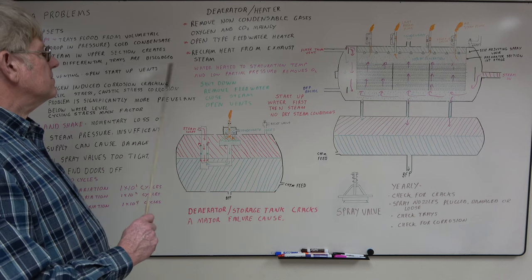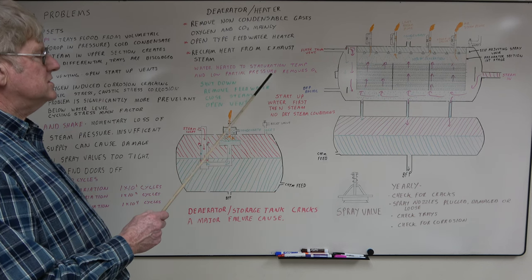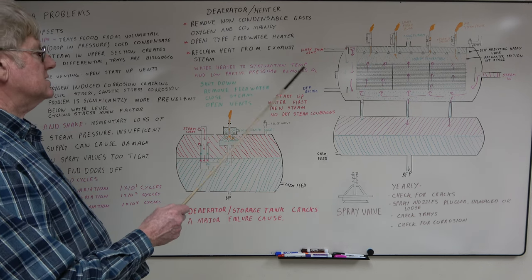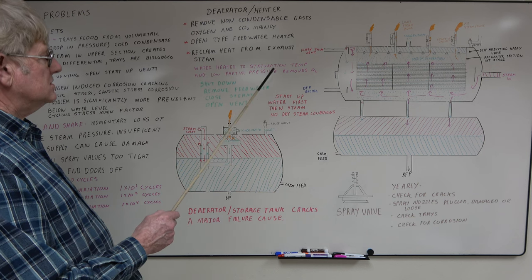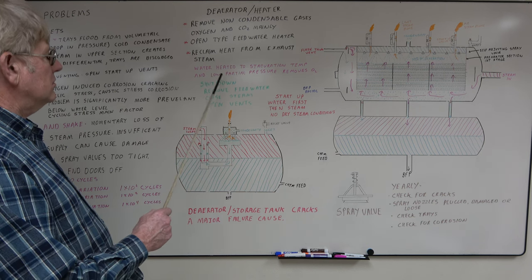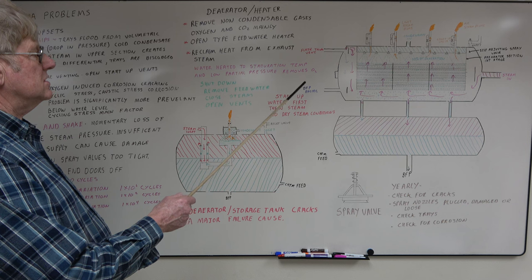The way they work, water heated to a saturation temperature won't hold any dissolved gases, so you heat the water to saturation temperature and the low partial pressure removes oxygen and carbon dioxide.